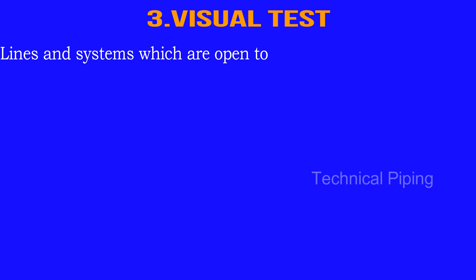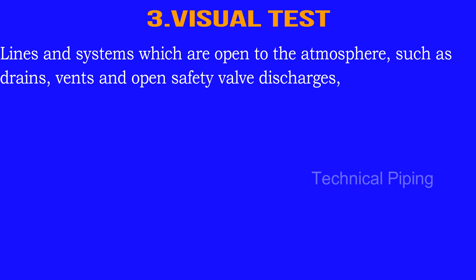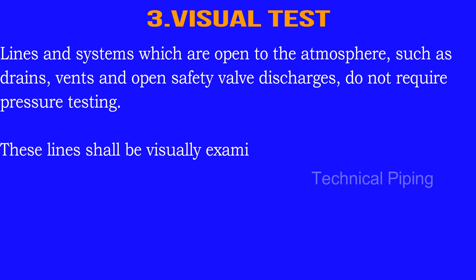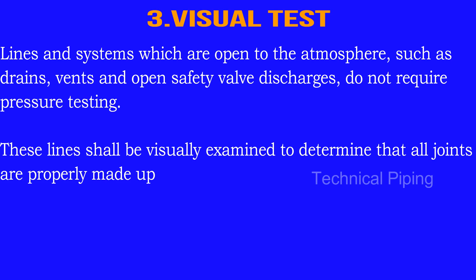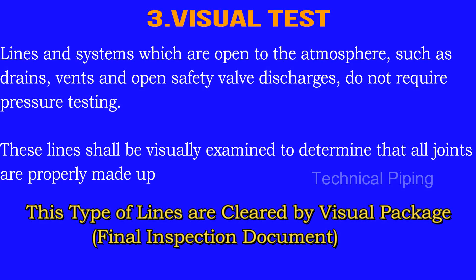Number 3: Visual Test. Lines and systems which are open to the atmosphere, such as drains, vents, and open safety valve discharges, do not require pressure testing. These lines shall be visually examined to determine that all joints are properly made up. This type of lines are cleared by a visual package final inspection document, based on project owner requirements.